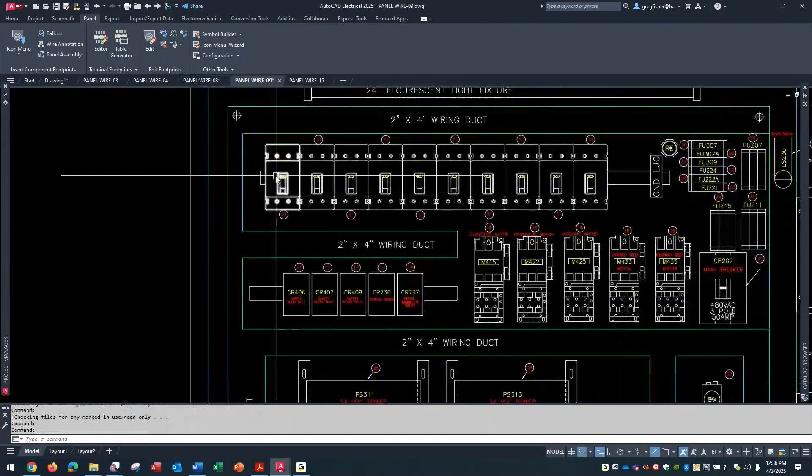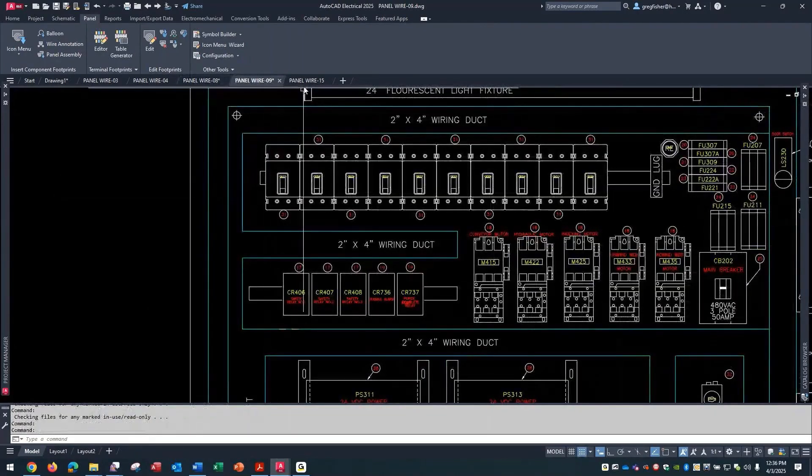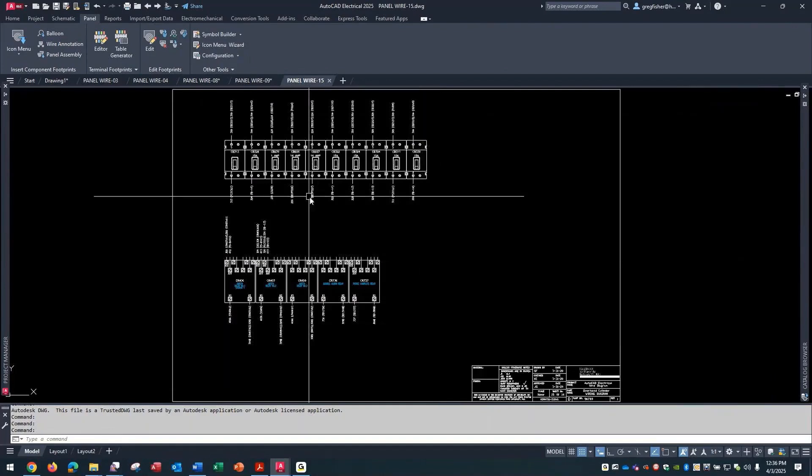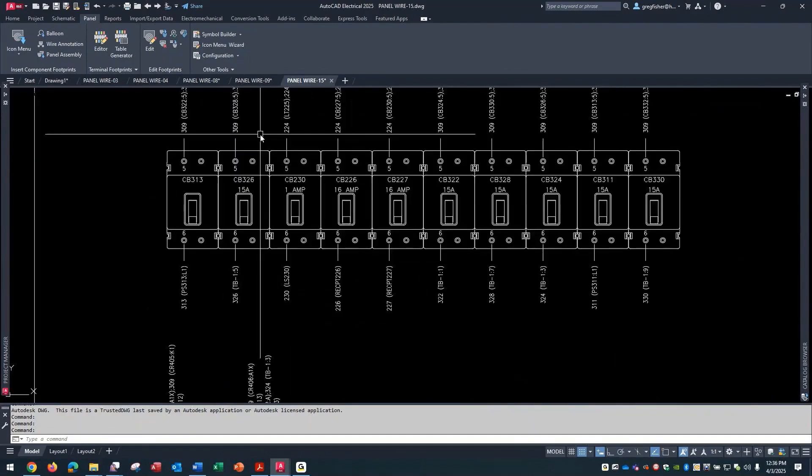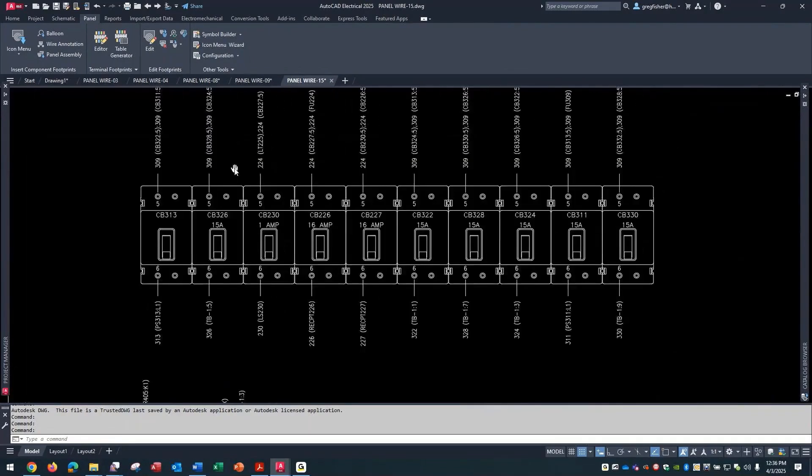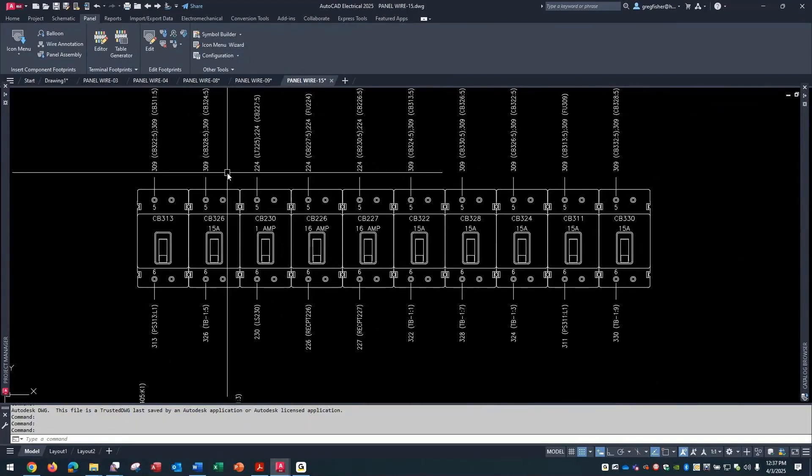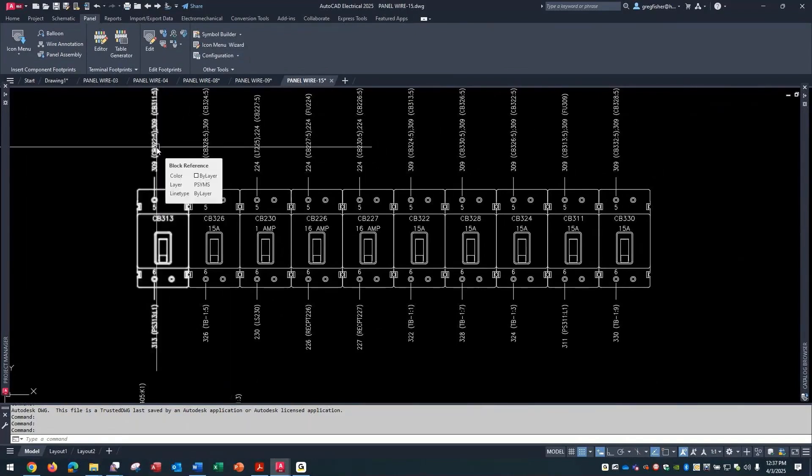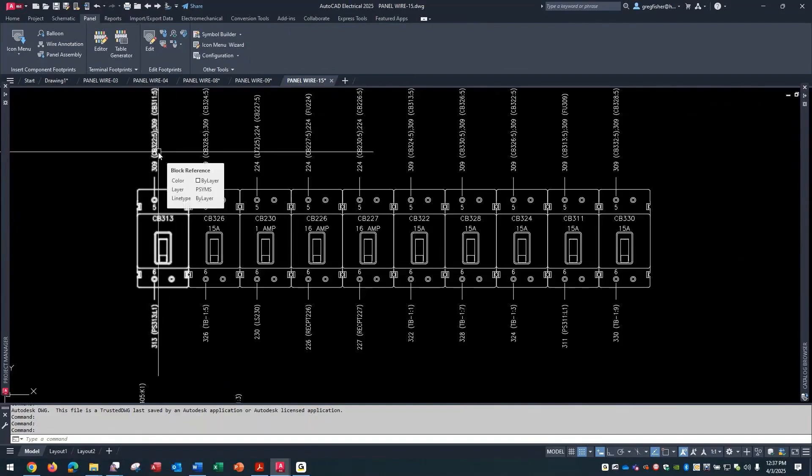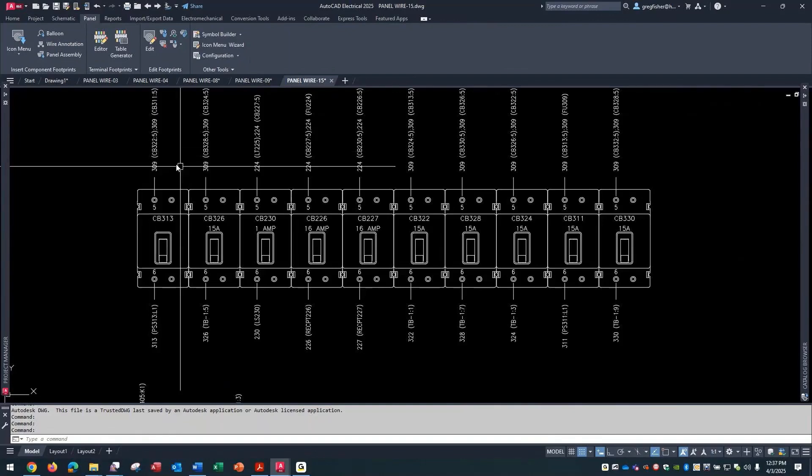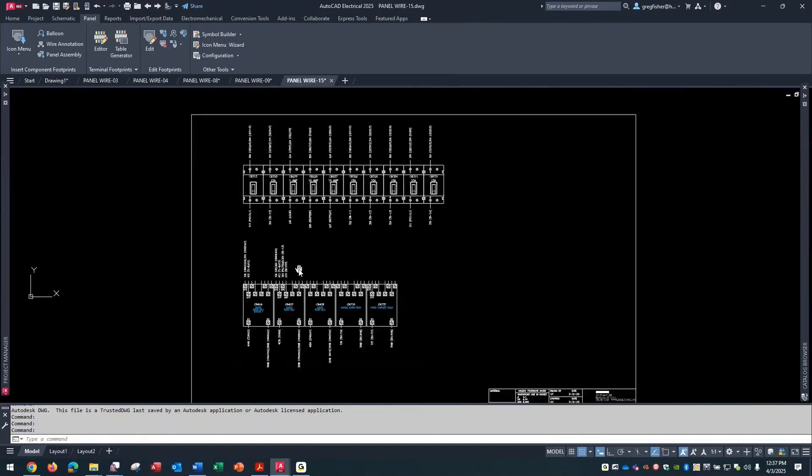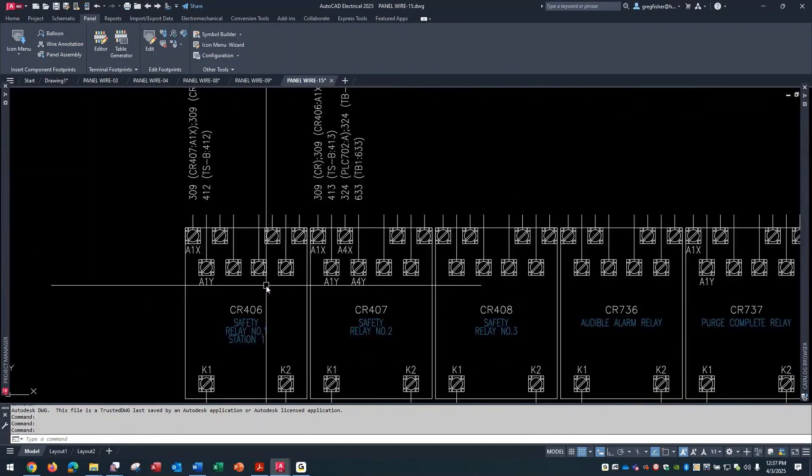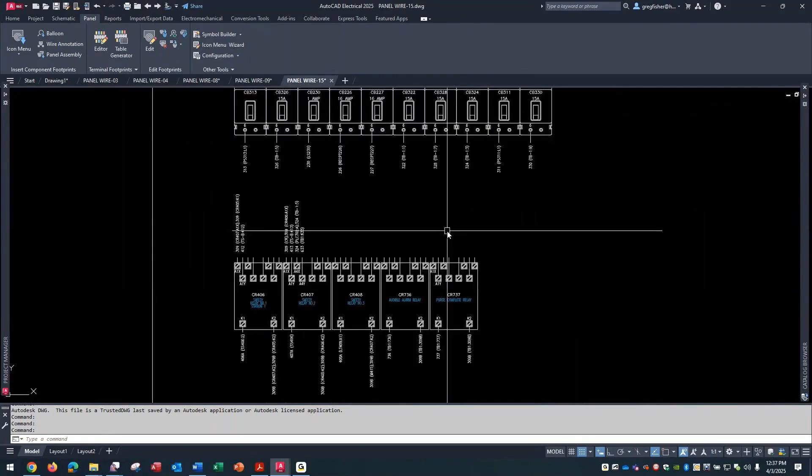You can get a lot more detail - essentially you can create a separate footprint symbol just to show the wiring detail. I've got these breakers up here, and it's telling me every terminal that I'm using on the breaker, the wire that's connected to it or wires, and I also had the tag and the terminal number mixed in there as well. Same thing with these relays down here. This is the detailed wiring information that I can get out of the schematic drawings.